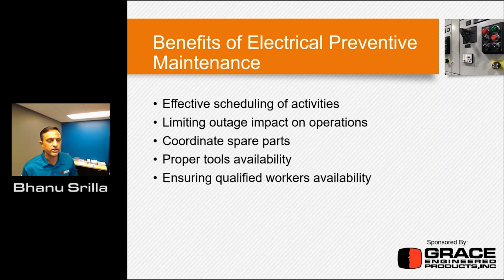So, benefits of electrical preventive maintenance: effective scheduling of activities. What I call effective scheduling here is basically that you perform these maintenance functions or plan these maintenance activities around your production outages, and the scheduling is done based on the prioritization of the equipment. So you limit outage impact on the operation, because if you know the maintenance condition of that equipment, you can basically predict when this equipment is going to fail or what the next thing is that we need to do. In that way, you can limit the outage impact on operations, so you can give more uptime to your manufacturing operations.